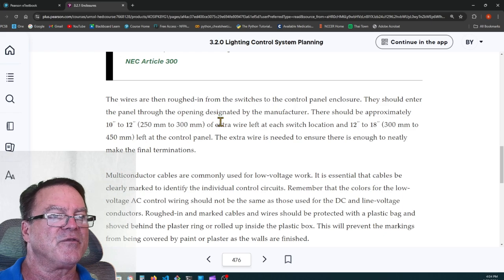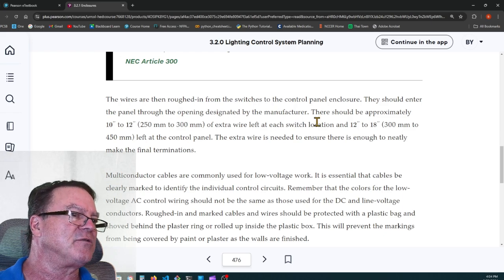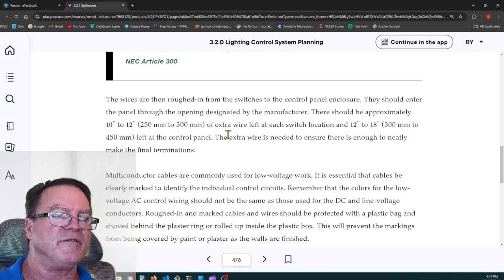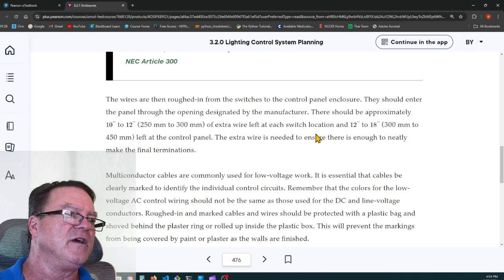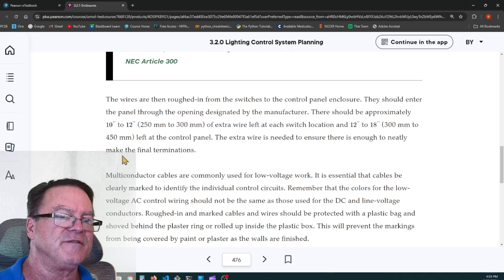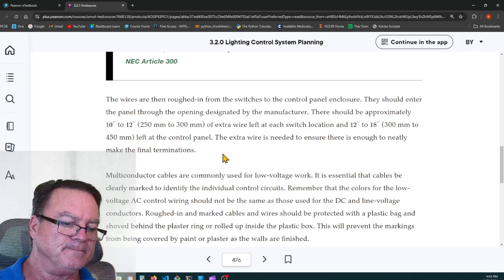The wires are then roughed in from the switches to the control panel enclosure. They should enter the panel through the opening designated by the manufacturer. They should be approximately 10 to 12 inches long of extra wire length at each switch location and 12 to 18 inches left at the control panel. The extra wire is needed to ensure there's enough to neatly make the final terminations.